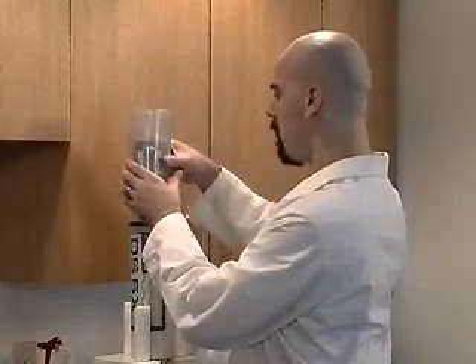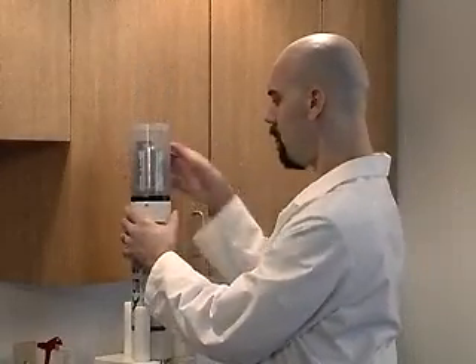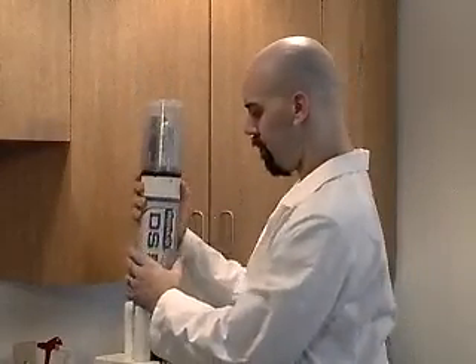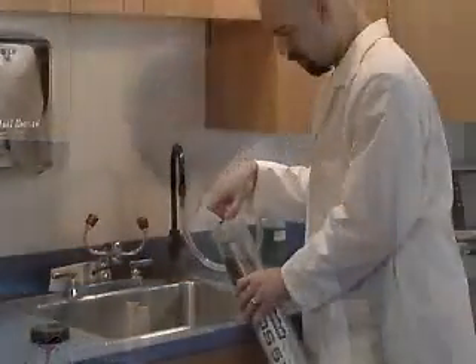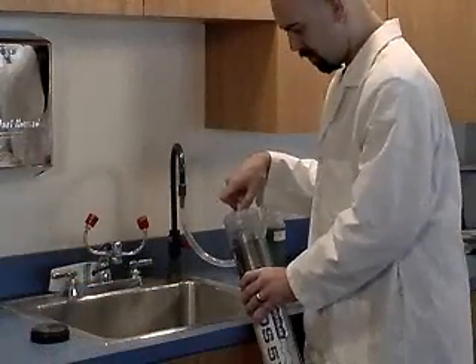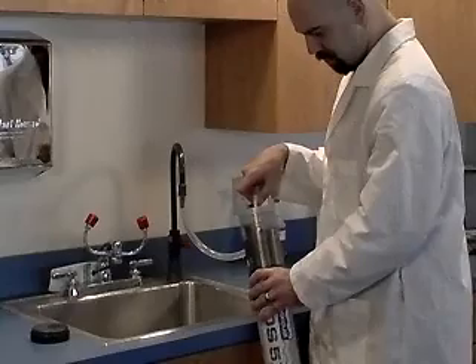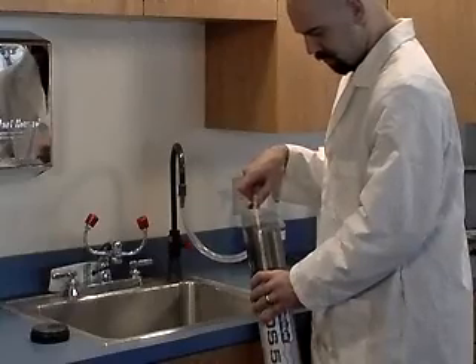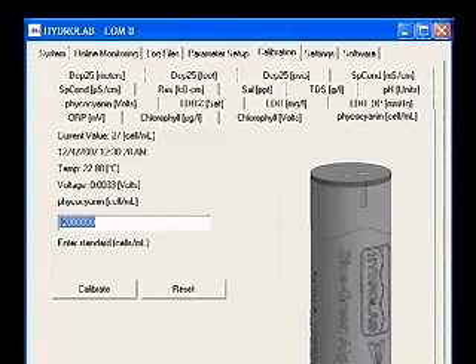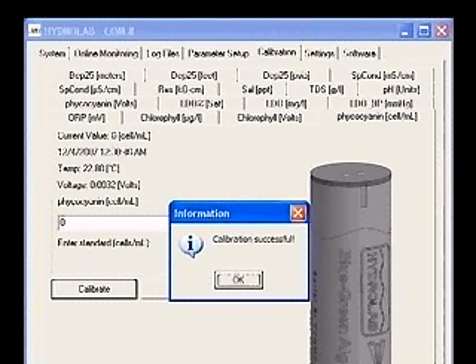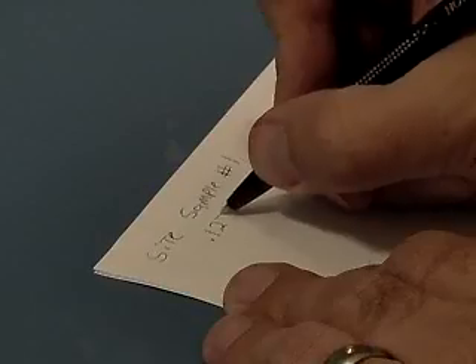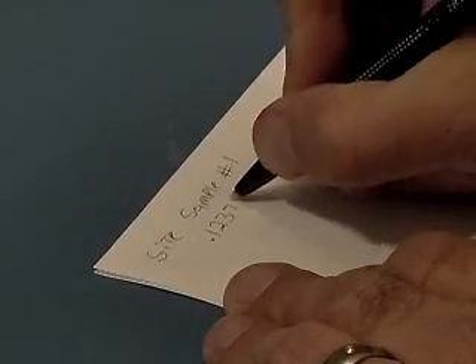Begin with a clean and dry sonde. Attach the calibration cup and fill it to the threads with sample water that has been filtered of all blue-green algae or optionally clean fresh water. Wait for 1 minute for the readings to stabilize. Type 0 into the box and click Calibrate. A calibration successful message will appear. At this point, record the voltage reading.